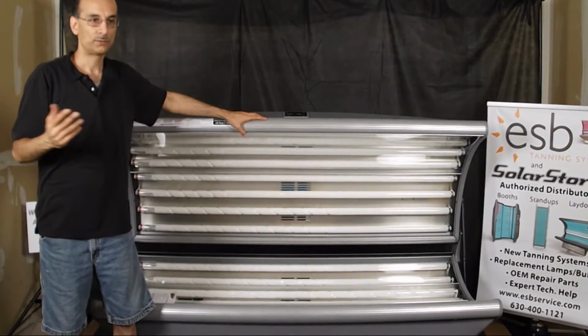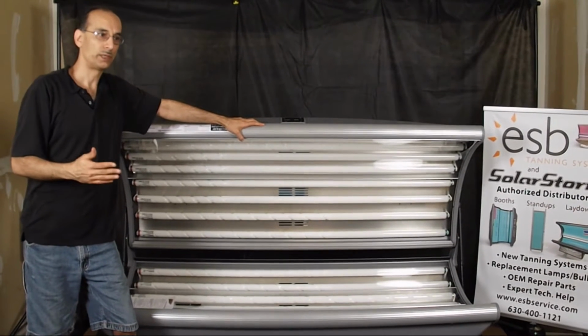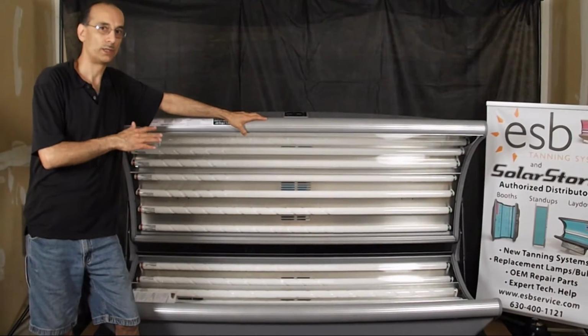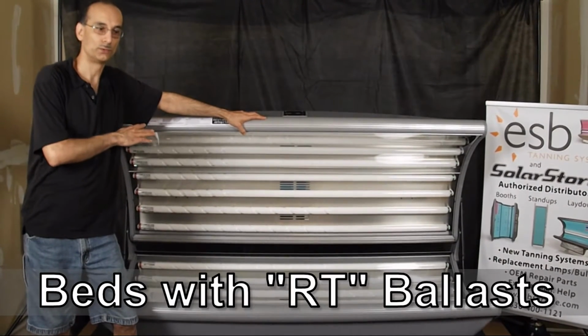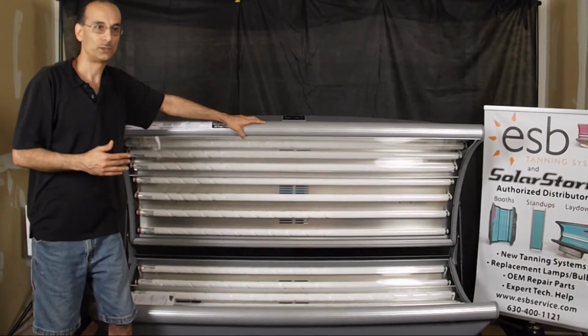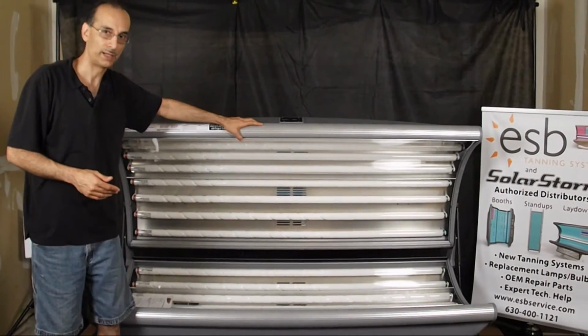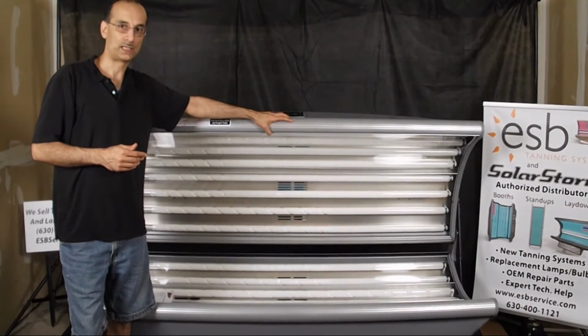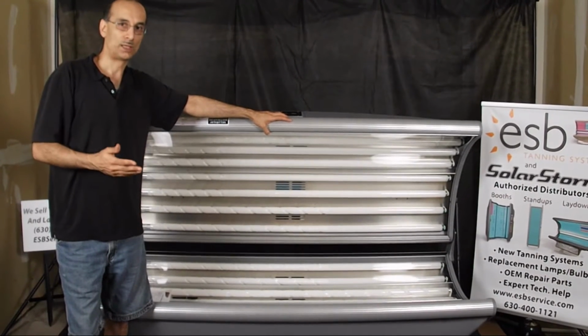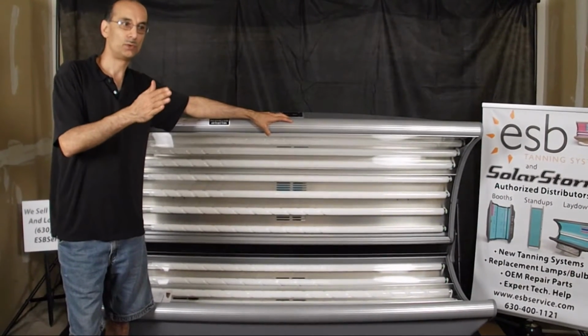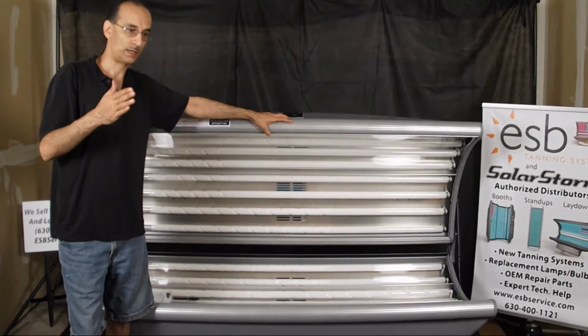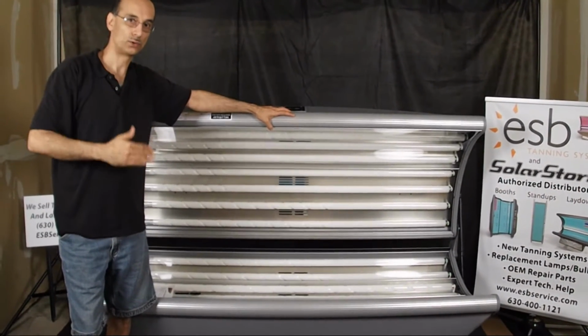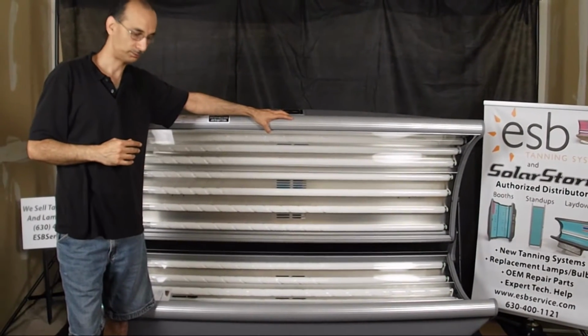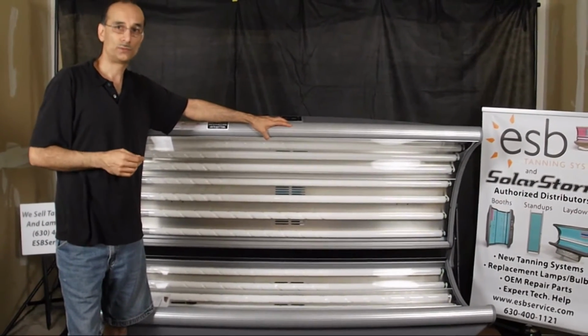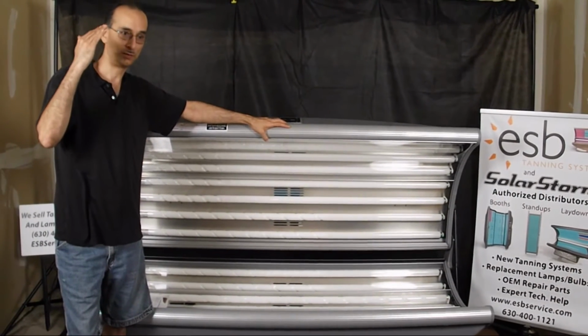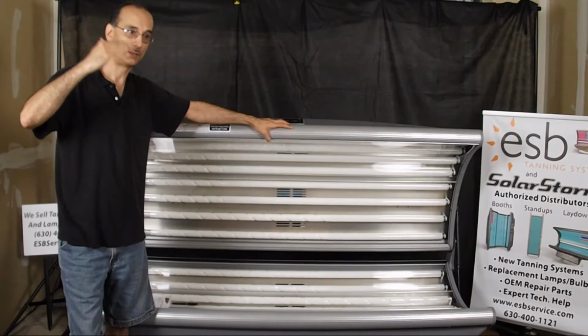Now, since 2005, ESB has incorporated some more modern electronics that don't require you to use buck boosters. So for almost the last 10 years, they have been pretty much a thing of the past. But I know a lot of people out there have older tanning beds, and especially if you're having electrical problems, that might help you to determine the root cause of that, if you have receptacle voltage that is simply too high or too low for what your bed is specified for. So again, that's what determines if you need a buck booster or not. Whether your receptacle voltage is within the spec or not and needs to be corrected.